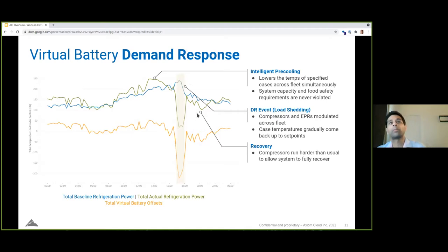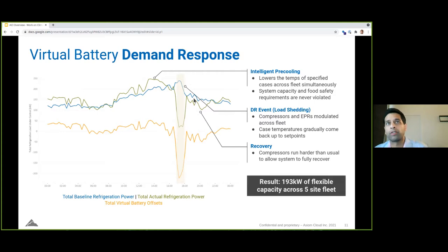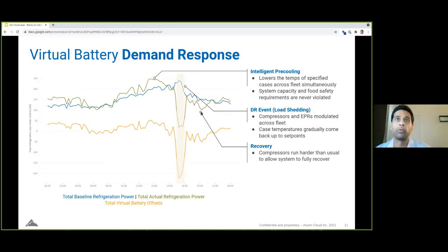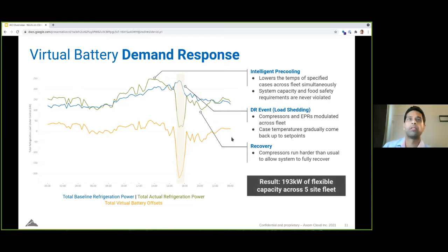And then what ends up happening afterward is that you get a recovery period during which the compressors have to run harder than they would have otherwise. So that makes sense because we've actually, quote unquote, depleted the battery. The system is running a little bit harder than it would have to get back to essentially its nominal state. But in doing so, we get 193 kilowatts of flexible capacity across a 5-site fleet. And so that can multiply quite a lot as the fleet grows.